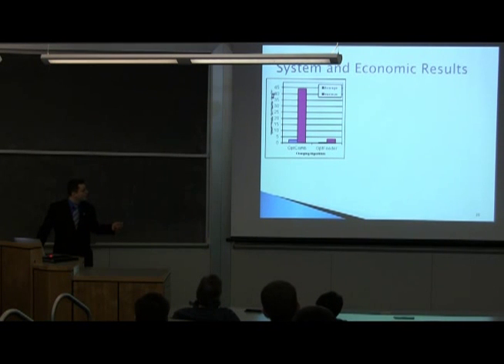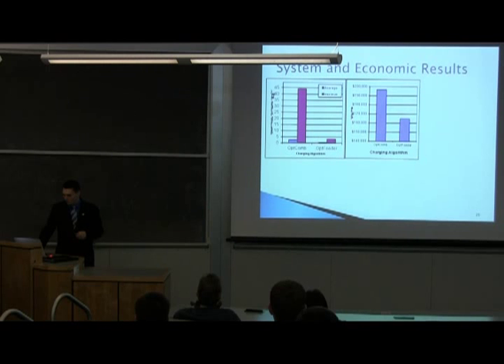Looking at the economics and the larger system, this is the peak load that would be added by the electric cars on the bulk power grid. Unconstrained could be up to 45 megawatts, whereas the average is about 2 megawatts. With the opt-feeder approach, the maximum is never above 5, and the average is less than 1. So from the bulk system perspective, this constrained optimization is much better for them too.